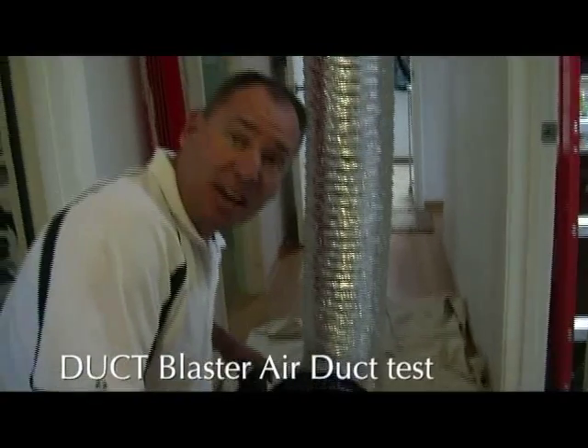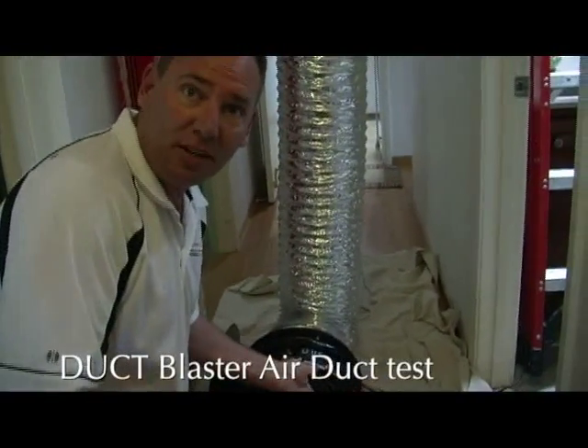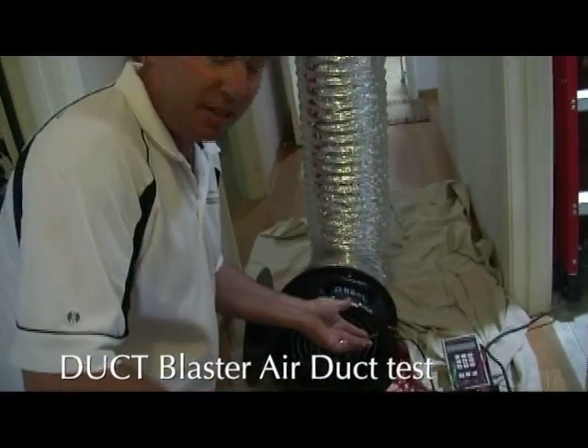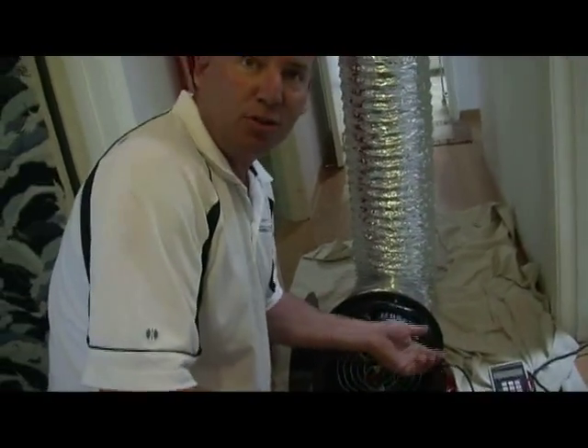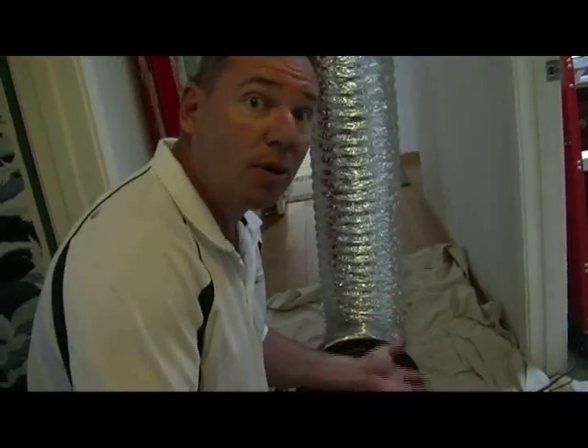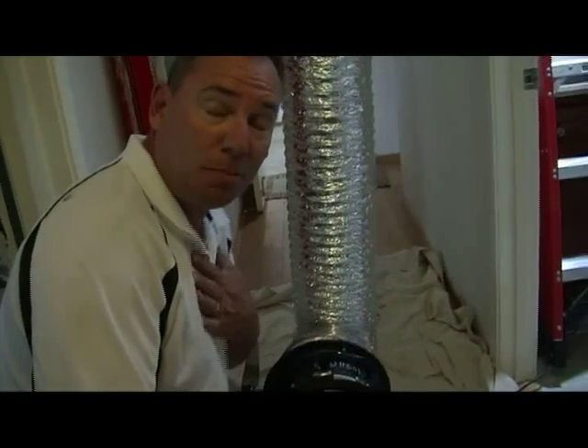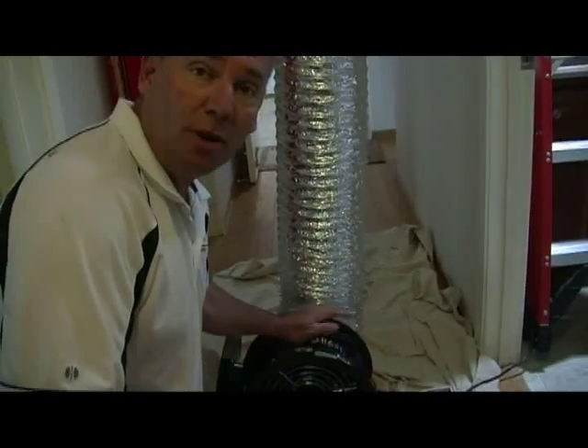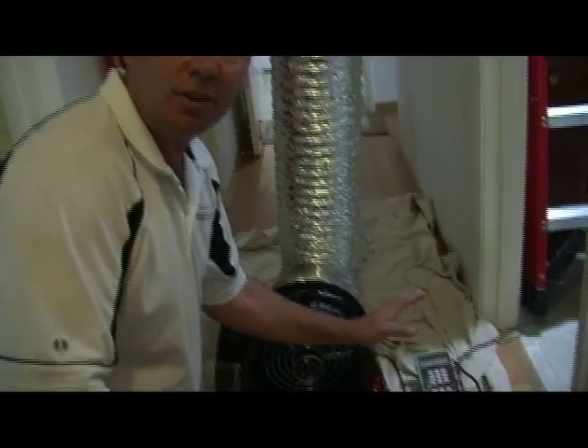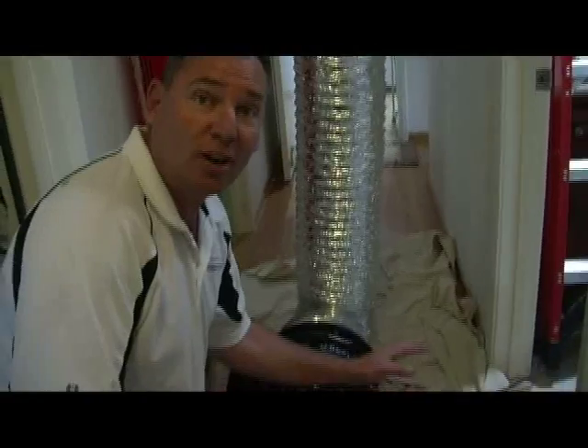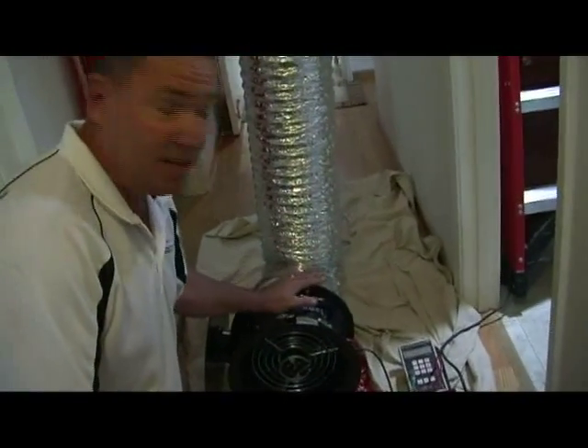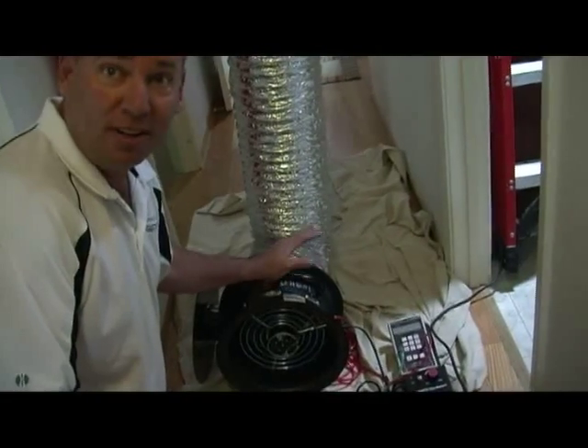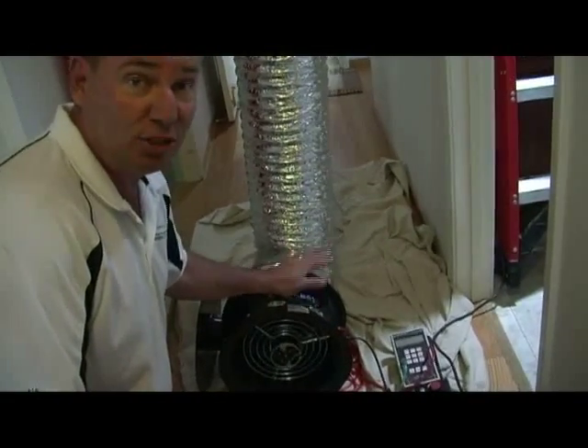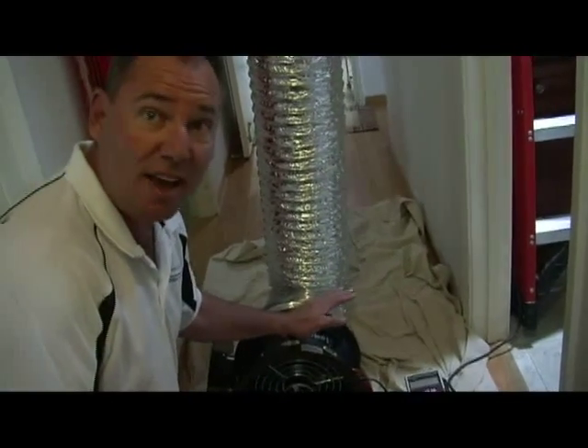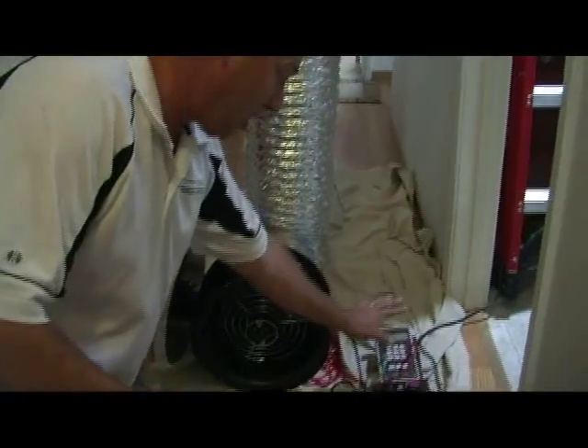The equipment that we have here is a duct blaster, and this part of the equipment allows us to measure the leaks in the heating and air conditioning ductwork that is in the home. As a performance contractor, this piece of equipment and this measurement is very important. I would say that the lion's share of your energy use is determined by the amount of duct leaks in your home. This piece of equipment does us a lot of justice in determining where we can save you money.